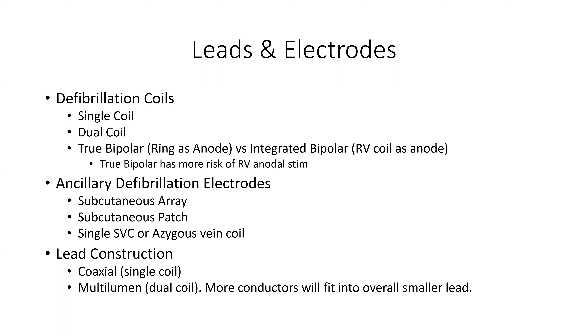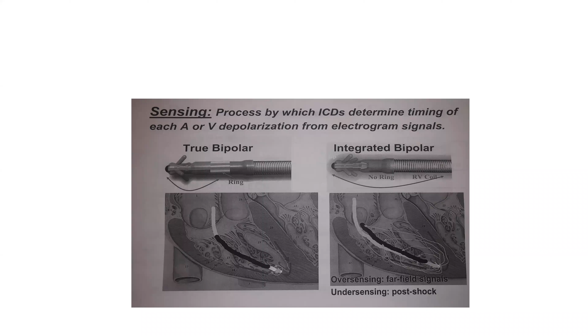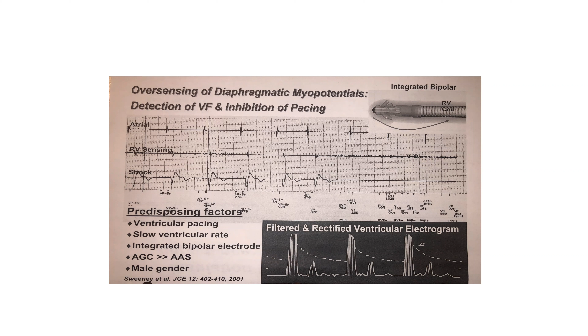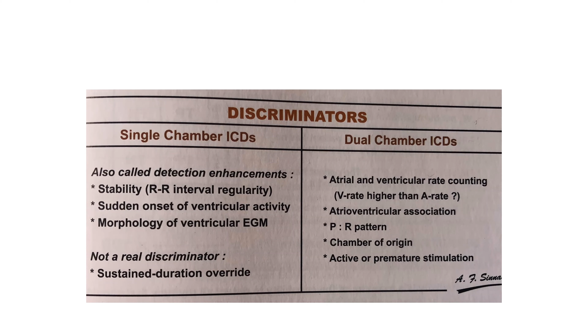This is a very quick schematic diagram of integrated bipolar, where you have more oversensing and also more undersensing. It may make the structure of the lead more simple, but then it could get us in trouble. And this is an example where diaphragm myopotential was sensed and led to no pacing. So, discriminators between single and dual chamber: if you have only one lead, the only way to differentiate between SVT and VT is using stability, sudden onset, and morphology. We'll look at that in the next slide. And if you have two leads, you can count the A and the V. You can notice which one starts first, the pattern of P and R, and then you can look also at whether it is caused by premature stimulation versus a sensed event.